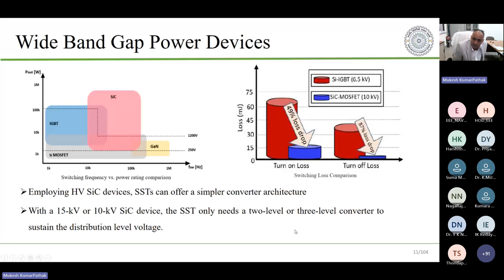You can see here a 6.5 kilovolt IGBT, a 2-level converter based SST can only interface this much voltage, 2.4 kilovolt. Because whatever the power electronics device, if it is 6.5 kilovolt, you cannot apply the same voltage to these devices. You need a factor of safety also. So that reduction comes to nearly 2.4 kilovolt. Whereas with a 15 kilovolt or 10 kilovolt SiC device, the SST only needs 2 or 3 levels to sustain the distribution voltage. That means 11 kV. You can directly use these devices for 11 kV with a 2 or 3-level system.